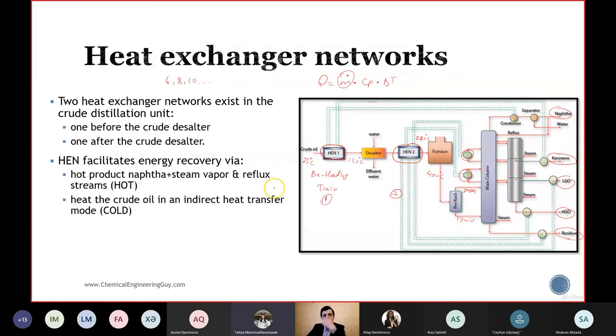And what about how much temperature is recommendable to increase in one heat exchanger? In terms of industry, let's say there is no such limitation. The outlet temperature is not what you calculate; it is your result. And for the heat exchange network, what is important is heat recovery, the percentage of heat recovery. If you can recover 90%, that is really good.